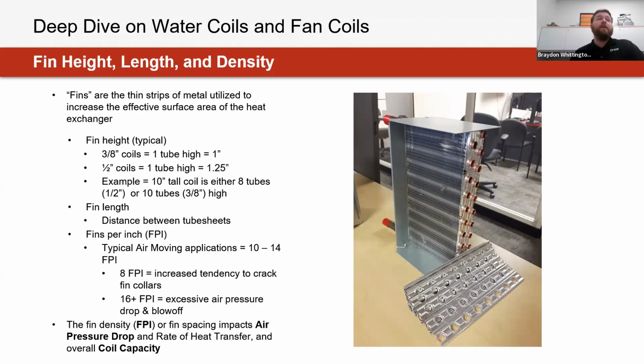Yeah, definitely interesting. I would say in terms of where you might see some 3/8 coil, it might be for some smaller coils within the industry, but more often than not, especially for terminals and fan coils, the typical industry standard is 1/2 inch tubes passing through those fins.